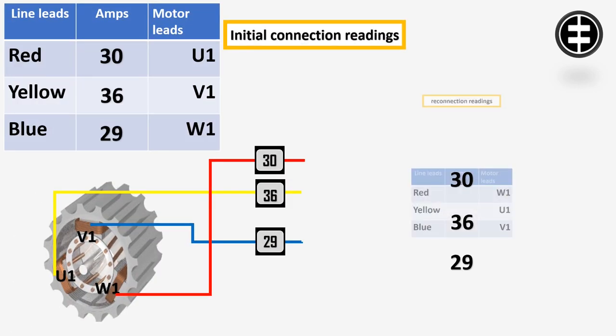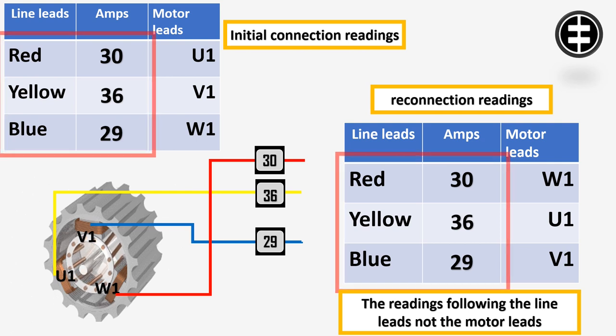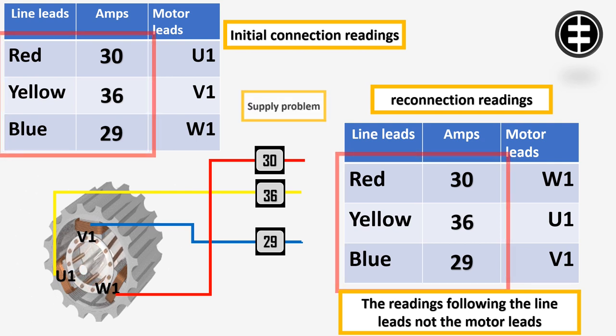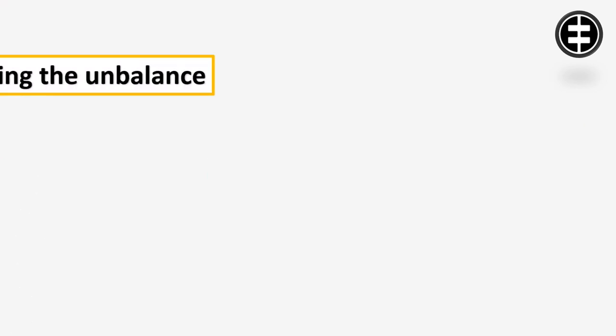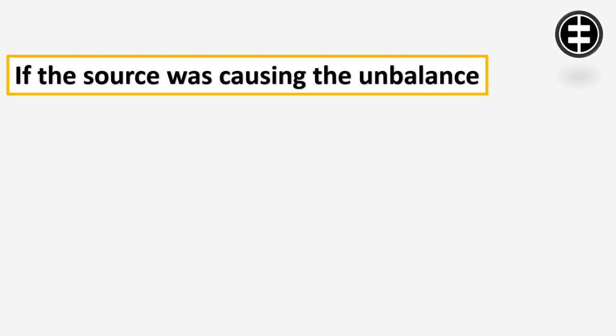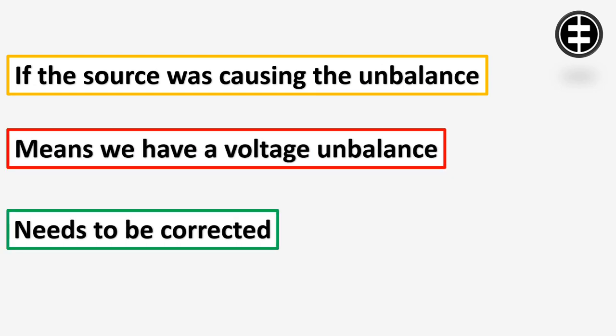If the high current and low current readings follow the same line leads, then the supply is the cause of the problem. If the source was causing the unbalance, that means we have a voltage unbalance which needs to be corrected.